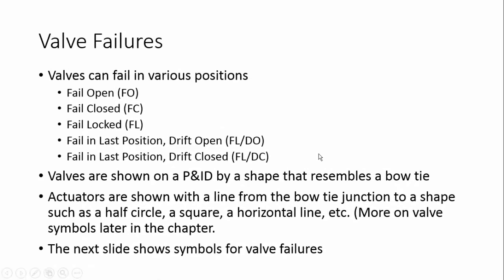Which leads you to the valve failures. So valves can fail, and again, we just talked about this last week. Valves can be fail open. They can fail close. They can fail locked. They can fail in the last position they were in and then drift open. Or they can fail in the last position they were in at the time of the failure and then drift closed.